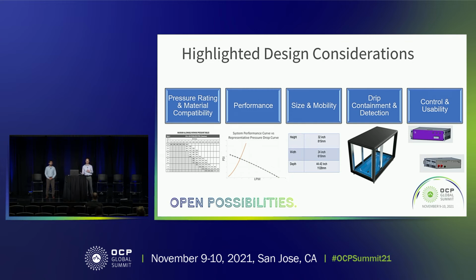Performance, I don't want to get too deep into this. I just do want to call out, when you're sourcing a pump for this cart, look at the performance curve, what pressure head it produces at what flow rates, and compare against your system pressure drop curve through your system. You do have to take into account that with the cart, there's going to be additional pressure drop inherent through the flow meter, bubble trap, everything in there. And so in sourcing those pumps, that needs to be taken into account and subtracted using some sort of fluid flow equation through pipes. Once that's predicted, source the pumps. Again, it would be good to test this cart against the actual system before deploying to multiple data centers.